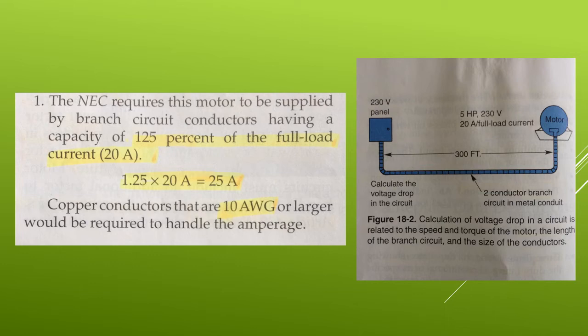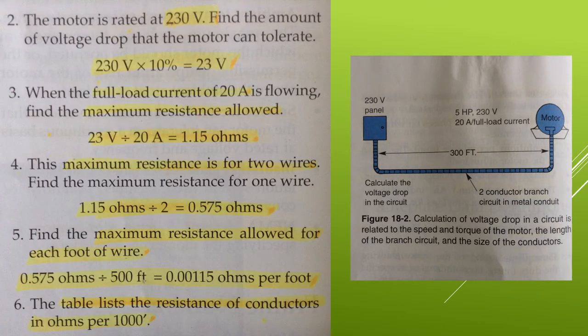Step 2, the motor is rated at 230 volts. Find the amount of voltage drop that the motor can tolerate. So we have 230 volts times 10%, or times 0.1, which is the same as 10%, which gives you 23 volts.